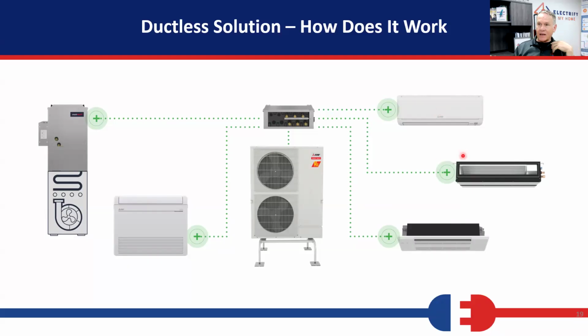I have to add up the capacity of all of these heads in order to match it to the outdoor unit. With some of the manufacturers, the heads go as low as 6,000 BTUs. Some of them only go down to 9,000 BTUs. What we found by doing hundreds and hundreds of load calculations is that bedrooms don't need 6,000 BTUs most of the time. Maybe on the coldest and hottest days of the year, they might need that if it's not already cool inside, but they only need that for a few minutes while they bring the air temperature up or down. Once they need to slow down and modulate and give you the effective benefit of a modulating system, they can't slow down far enough.